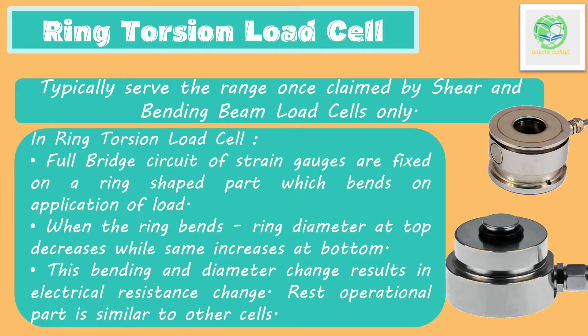In the case of a ring torsion load cell, full-bridge circuit strain gauges are bonded to a ring-shaped part which will bend when a load is applied. While bending, the ring diameter at the top decreases while the same increases at the bottom. In this whole process, the electrical resistance changes, which enables measurement of the load applied.